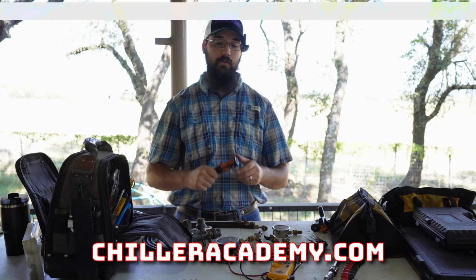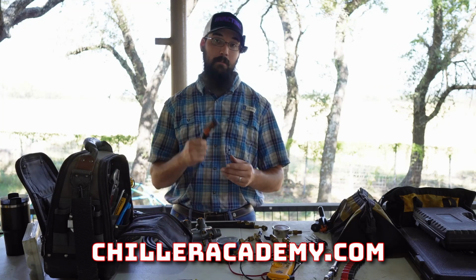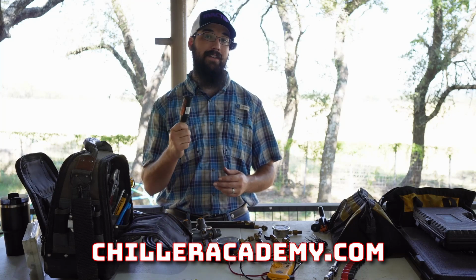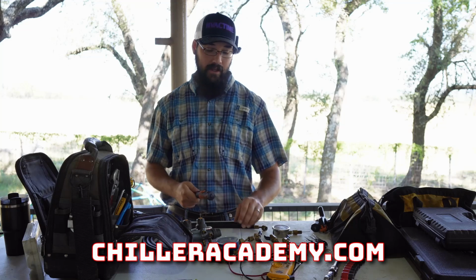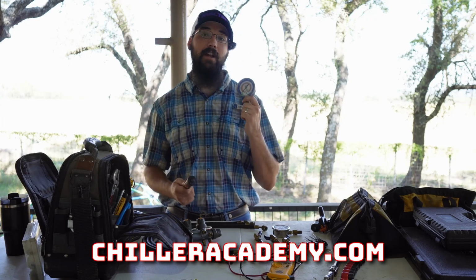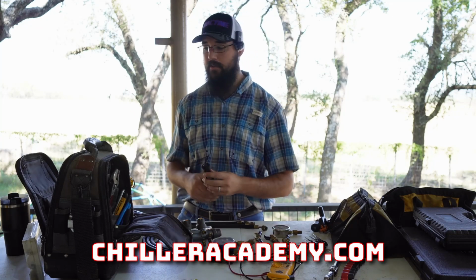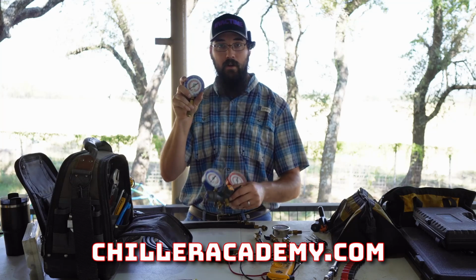That's one of the things you need to be aware of when going with either digital or Bluetooth. Tool manufacturers have done a lot to try to minimize that lag time, but it can't take away the fact that it is still there. Half a second of delay is still half a second, and depending on our circumstances, we can gain a lot of pressure in half a second that genuinely has an impact on what we're calibrating. Now, we're kind of splitting hairs there. Back to the manifold conversation.